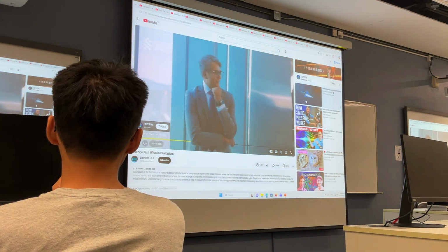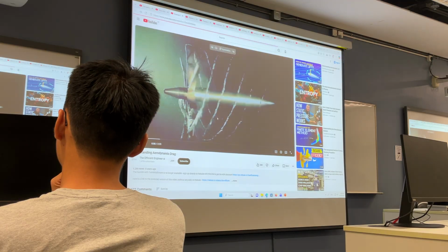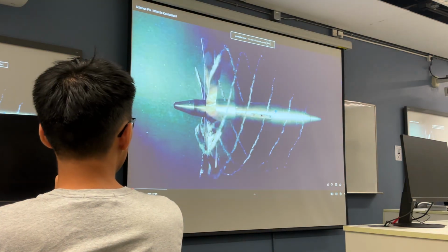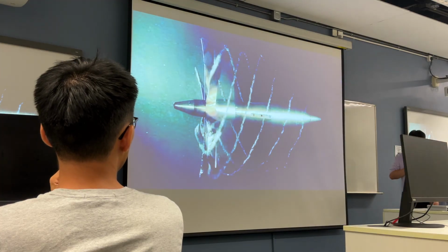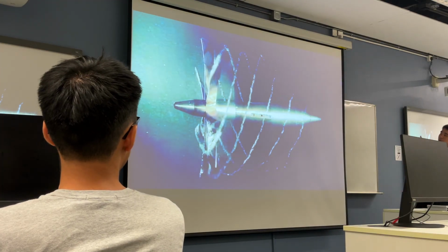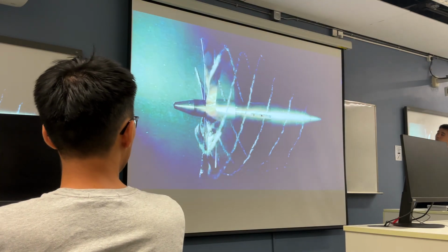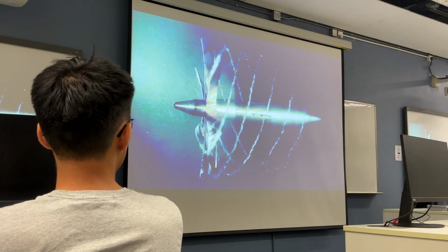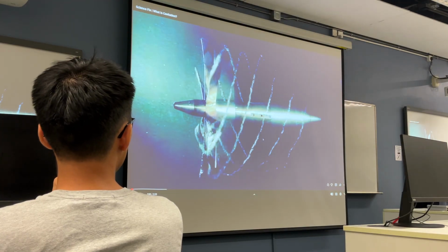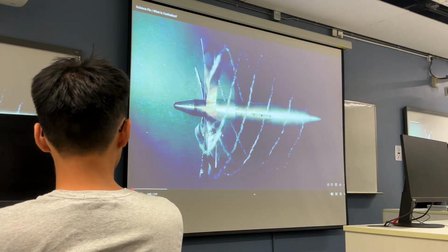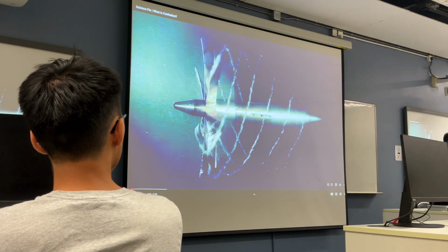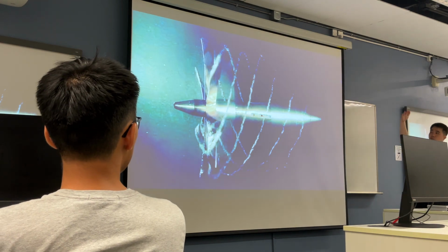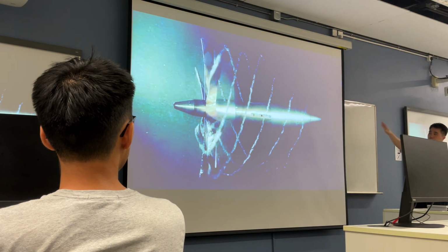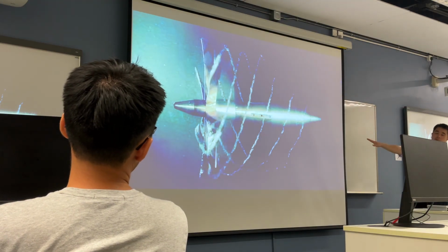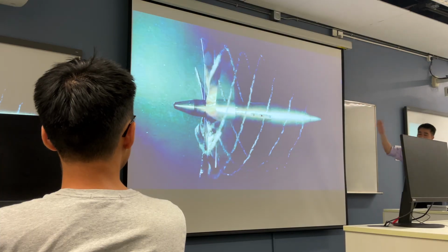Now the cavitations of the pump. Here is a video showing an impeller rotating inside the water. You see the strip here, it's like an air bubble. It seems this propeller is already submerged in the water, and there is no source for an air bubble. I can tell you this is not air, this is vapor. Strictly speaking, this is vapor, it's not air.